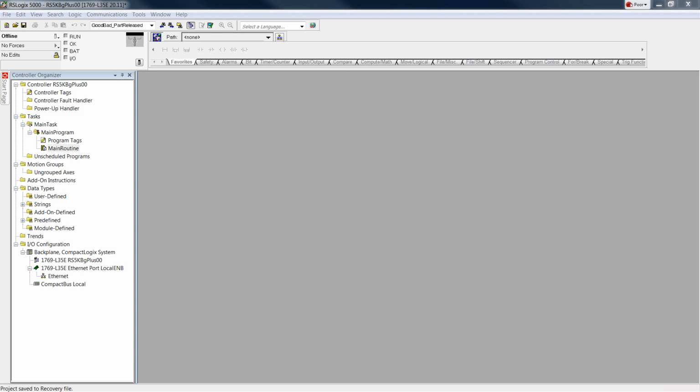We also introduced the first, or the original, 5 programmable logic controller instructions that literally simulated a relay controlled system. And those symbols look like a normally open contact, normally closed contact, a relay coil, and then symbols for the latching coil and unlatching coil of a latching relay. So the first 5 instructions, I refer to them as true if on, true if off, energize output, latch and unlatch, or set bit and reset.